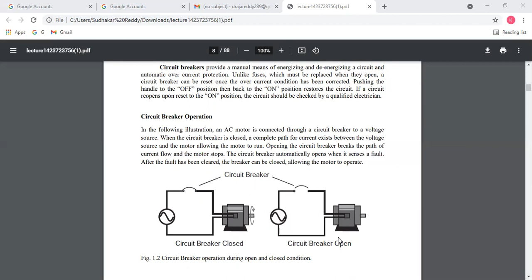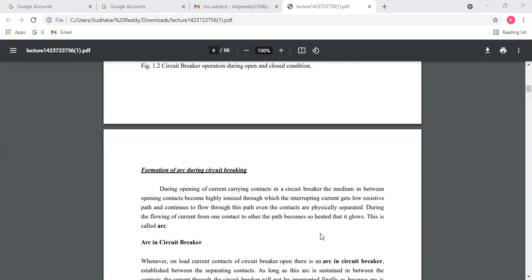Next, formation of an arc during circuit breaking. During opening of the current carrying contacts in a circuit breaker, the medium between the opening contacts becomes highly ionized, through which the interrupting current gets a low resistance path and continues to flow even though the contacts are physically separated. During the flow of current from one contact to the other, the path becomes heated, and the discharge generated in this path is called an arc. Now, what is an arc in a circuit breaker?